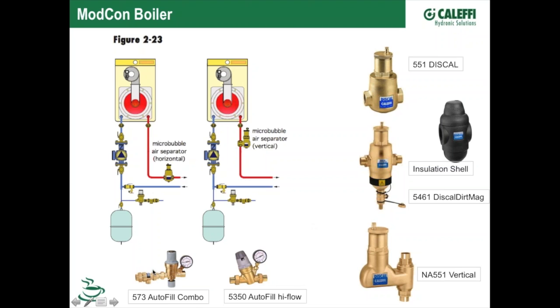An example of our two, again, autofill combo over here with the backflow on it and the high flow here. A nice point to put that in the system is right at the point of no pressure change, where the expansion tank ties into the piping. That's a good place to put your fill valve. This is a combination device that does both dirt and air. We'll talk about that a little bit more and some of the advantages of that.